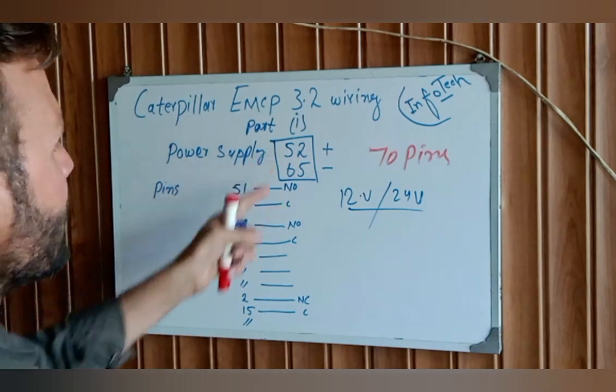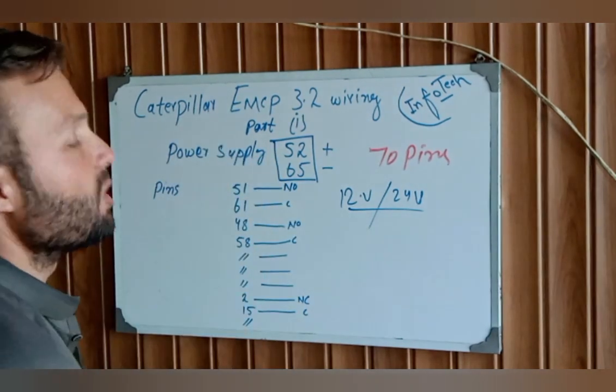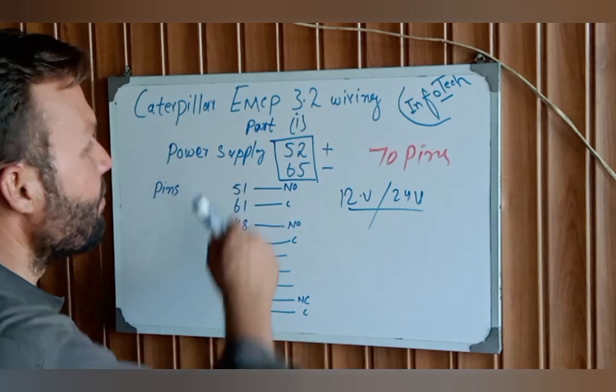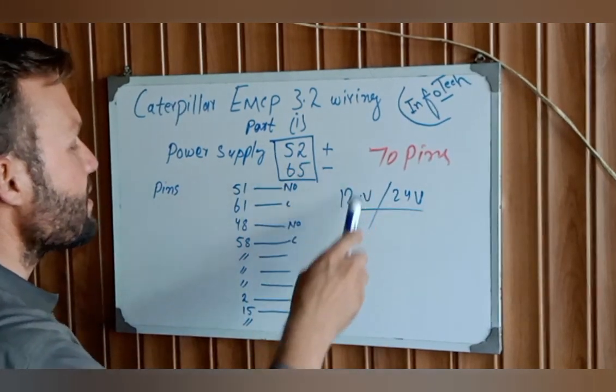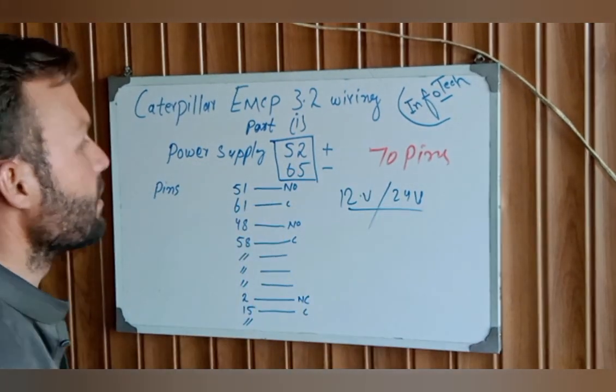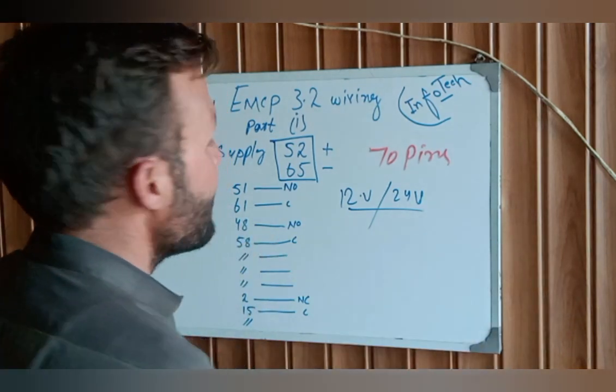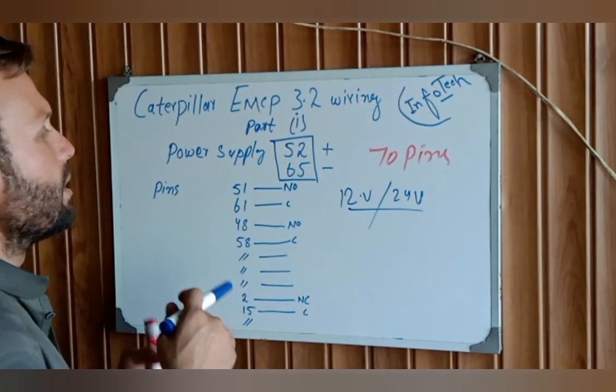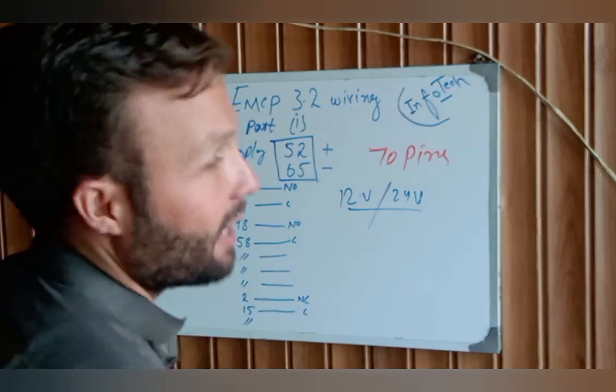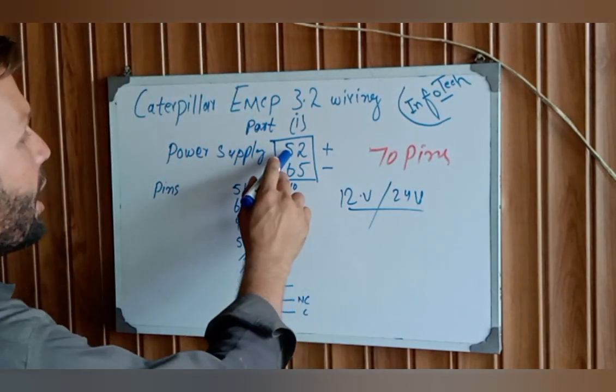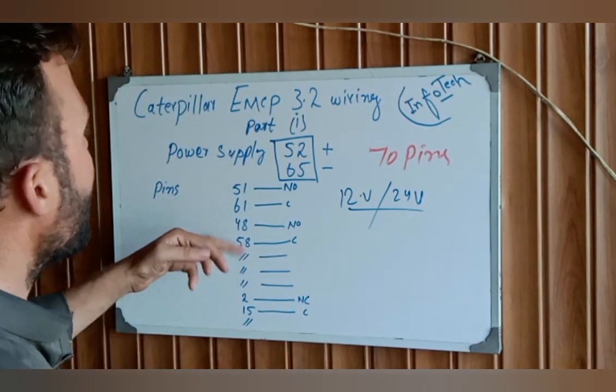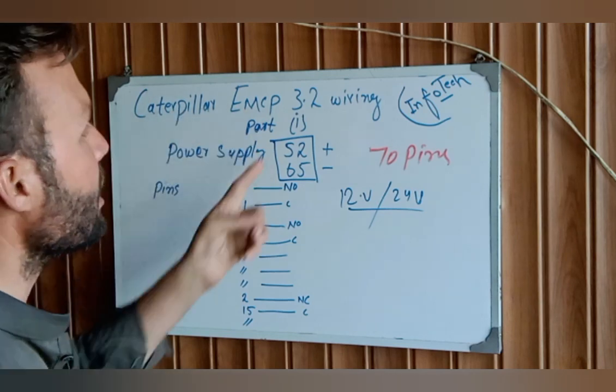Take the reading with the multimeter - you should get 12 volt or 24 volt. If you don't have supply on these two pins, your EMCP will not open. You trace these two wires step by step and check where the wire is cut or broken, then reconnect and check it again.